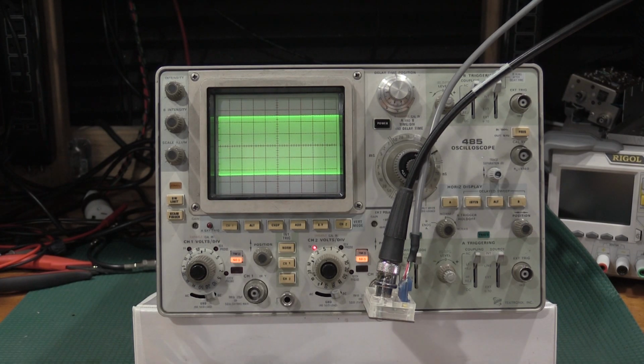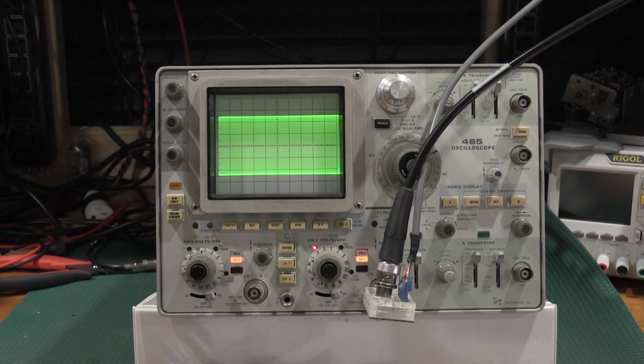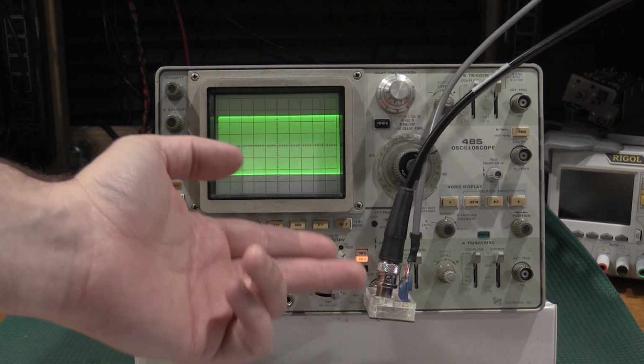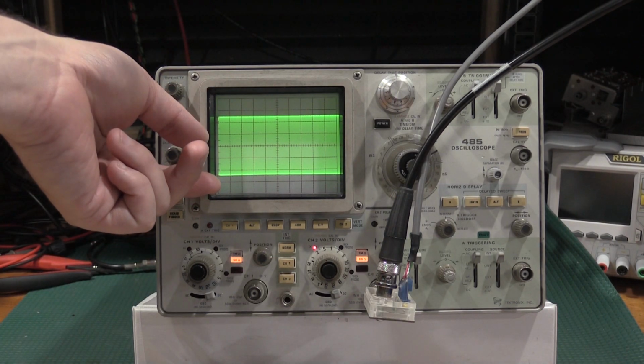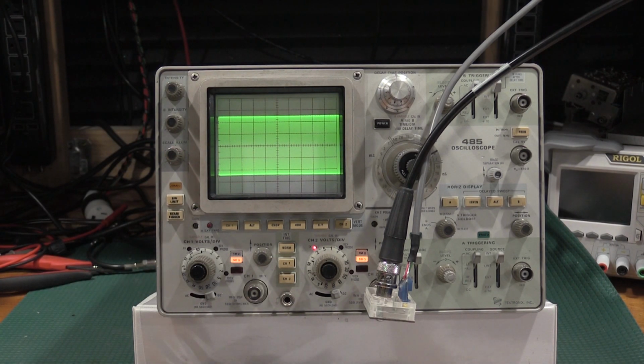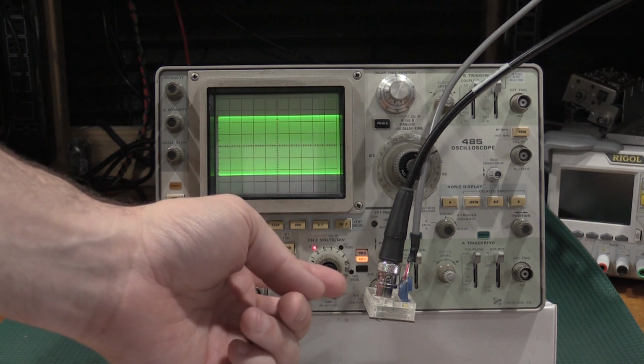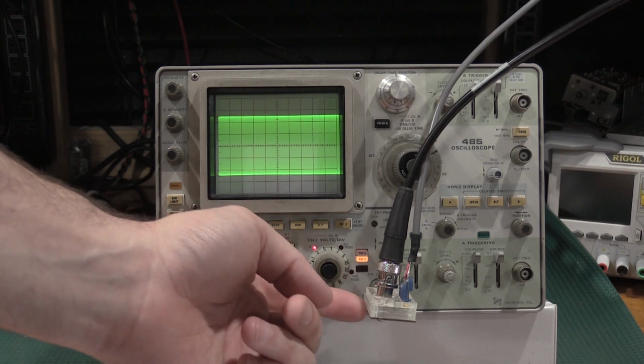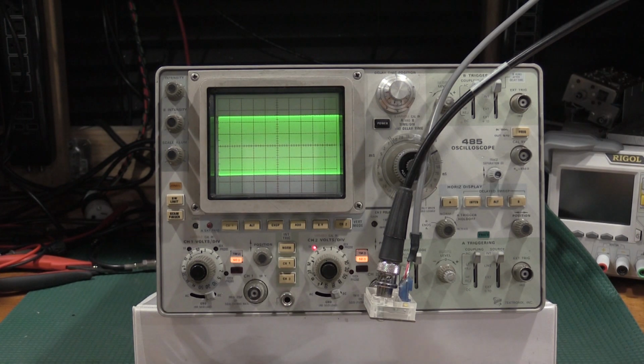Now, the thing with the leveled sine wave generator is, and this is the important part of why I needed the SG504 up and running, is I know the amplitude didn't change, just the frequency. You'll notice the scope dropped, but that's because of the frequency response of the scope. That's expected, and actually exactly what we're testing. But I know, because this is leveled, that the set amplitude at the jack is the same. That's why some function generators, signal generators, things like that don't do this test very well. Their accuracy of the level is not that great. Also not designed to be that great.